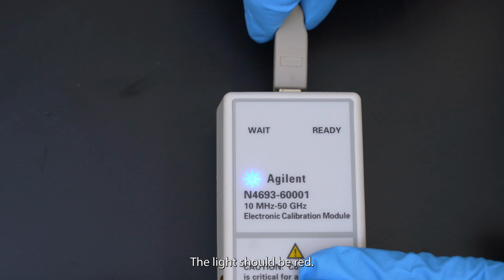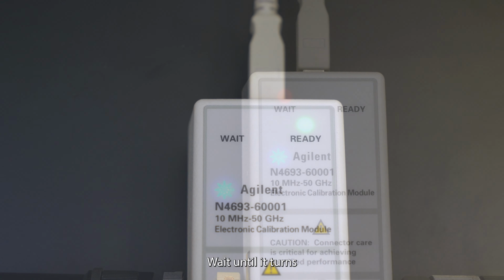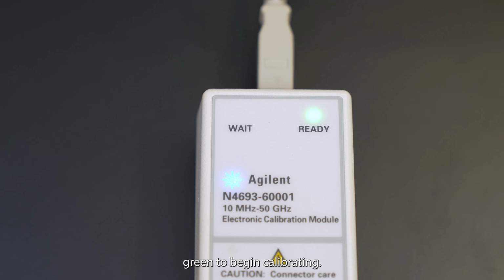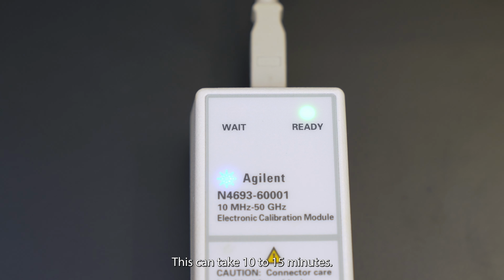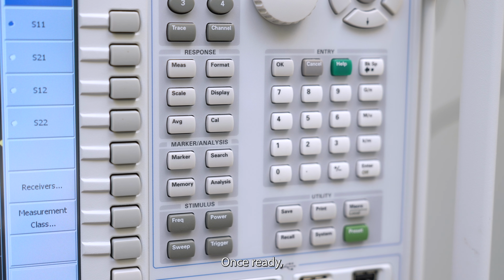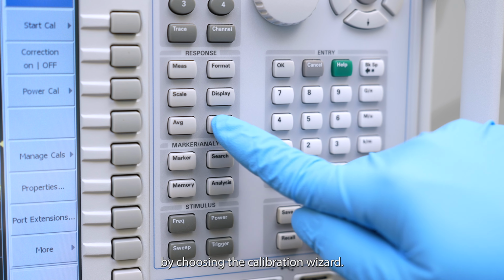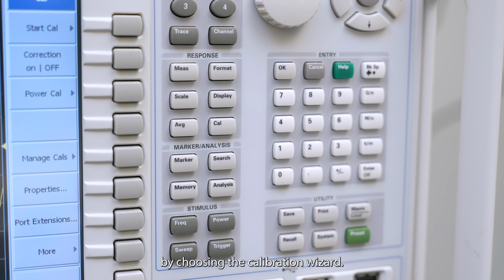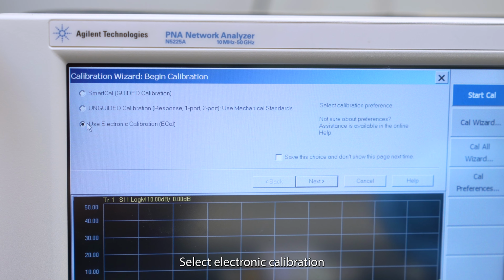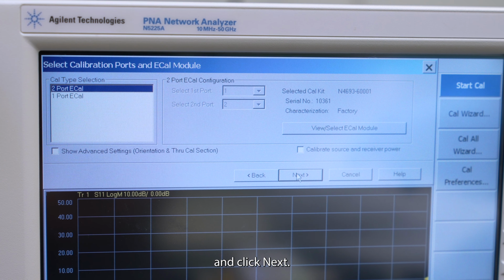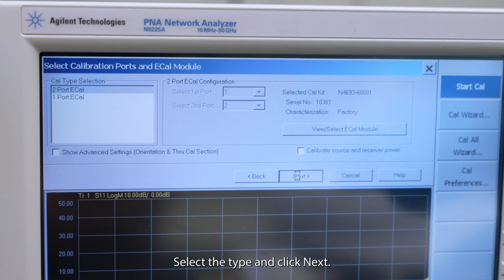The light should be red. Wait until it turns green to begin calibrating. This can take 10 to 15 minutes. Once ready, set up the calibration by choosing the calibration wizard. Select Electronic Calibration and click Next. Select the type and click Next.